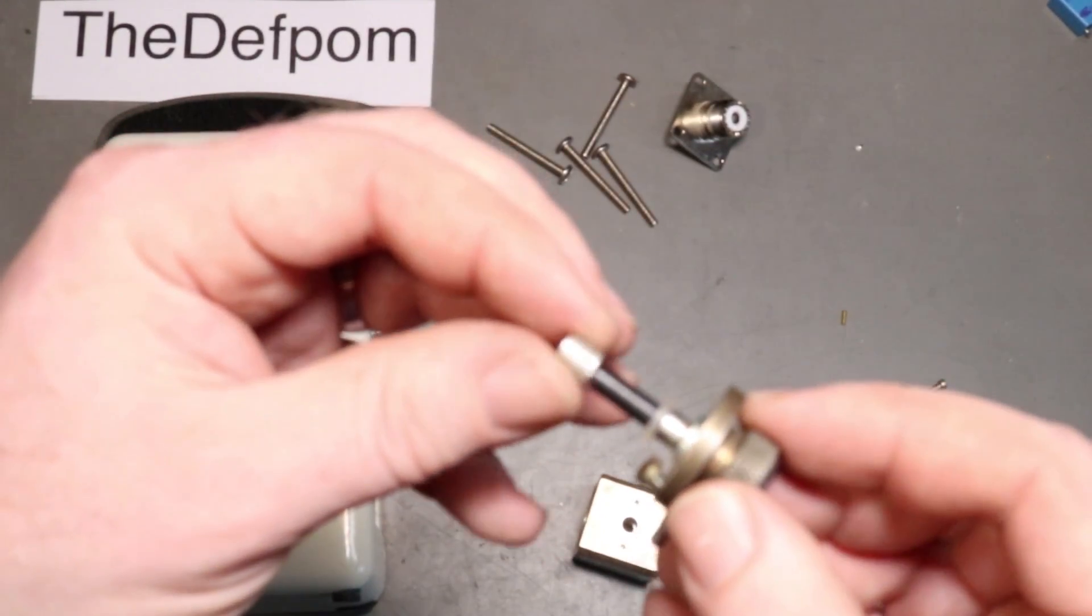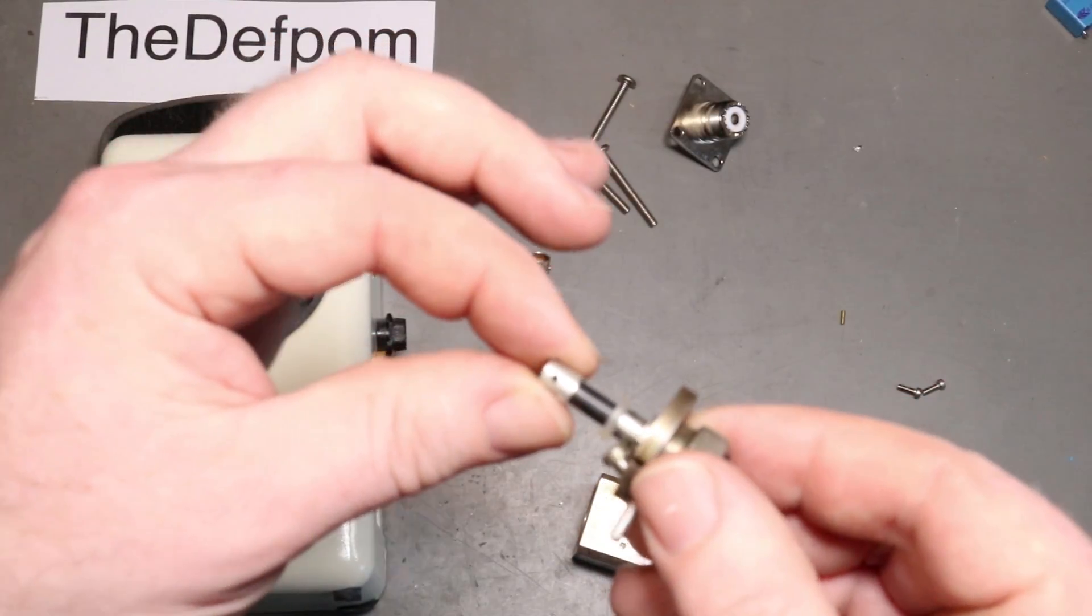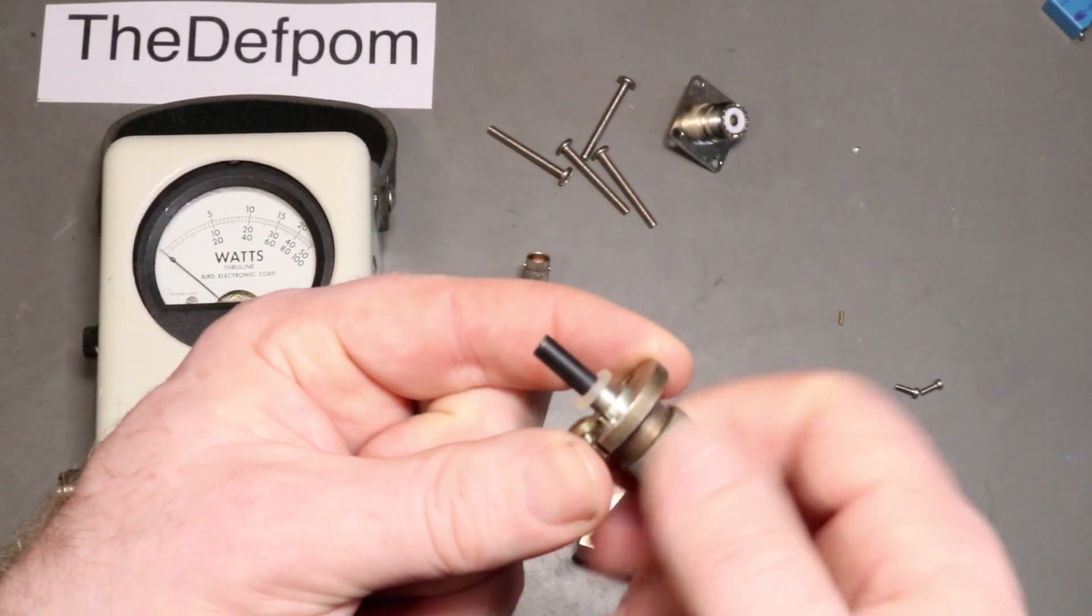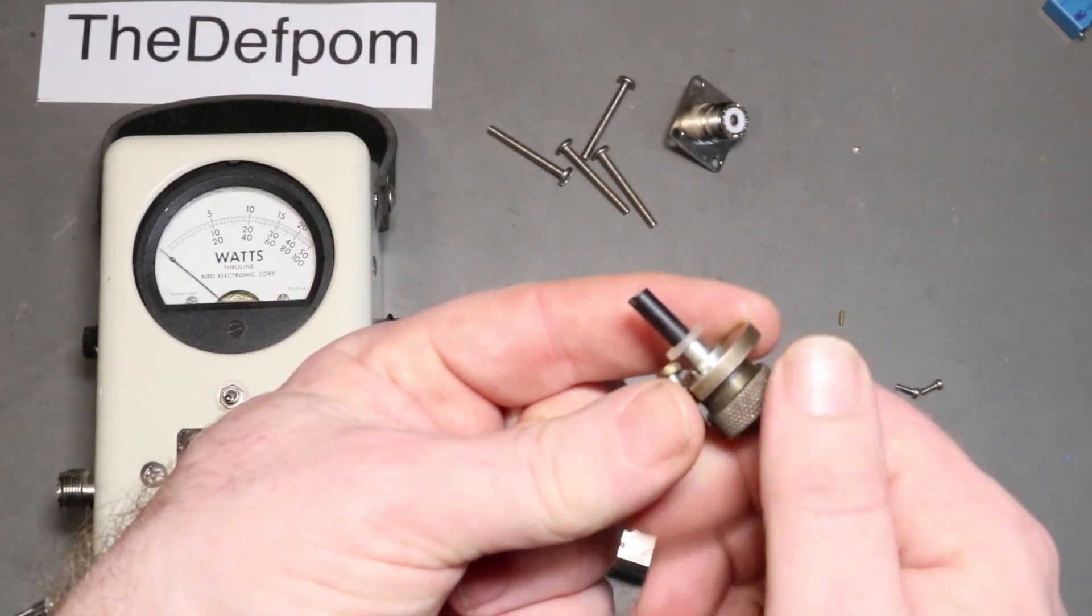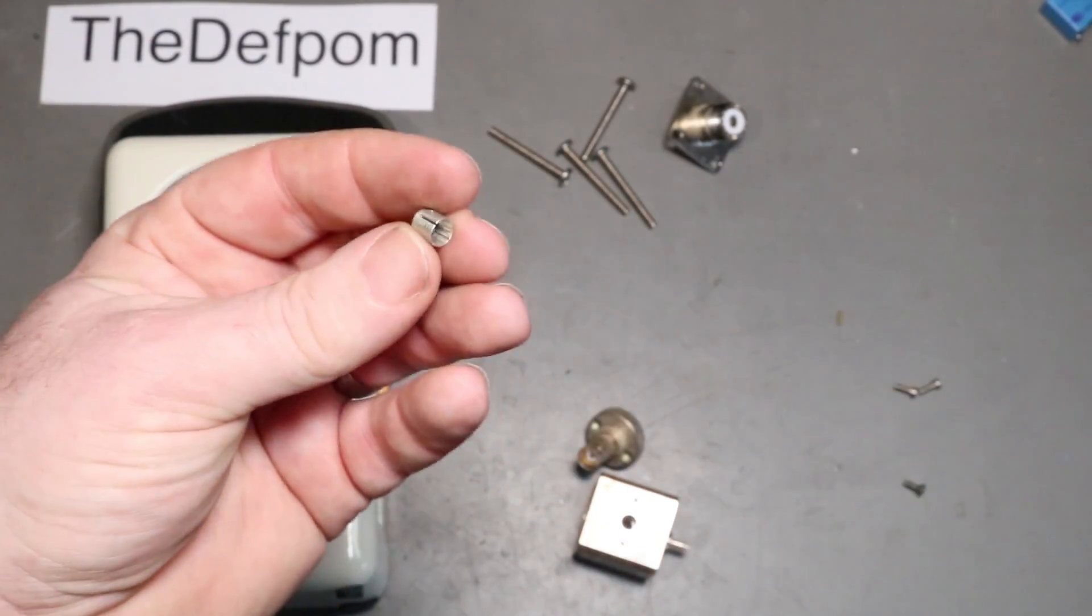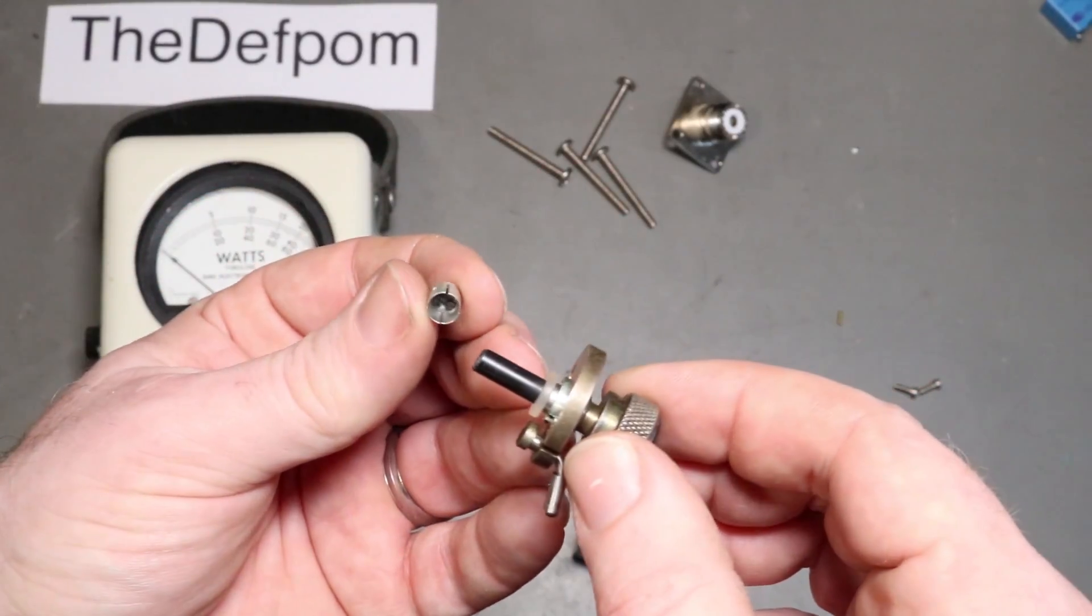It's got a hole for the pin - the back half is broken off, it's still inside here. There's supposed to be a pin through it to attach the end of that shaft. So when you wind this in and out, it winds the shaft in and out in order to slide this in and out to create a change of proximity gap between the tap-off point and the main conductor in the center. That's how the thing works, but it's broken off.